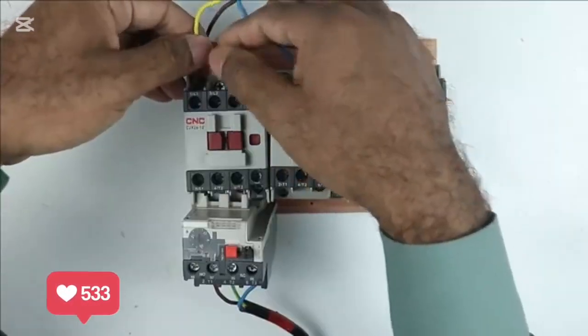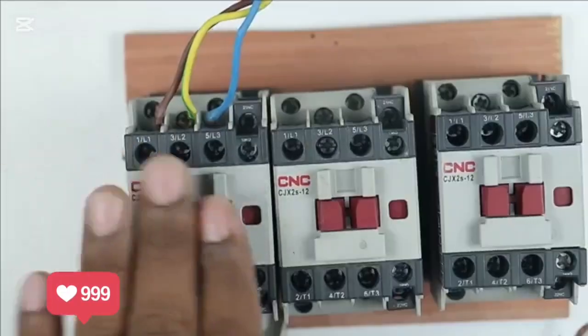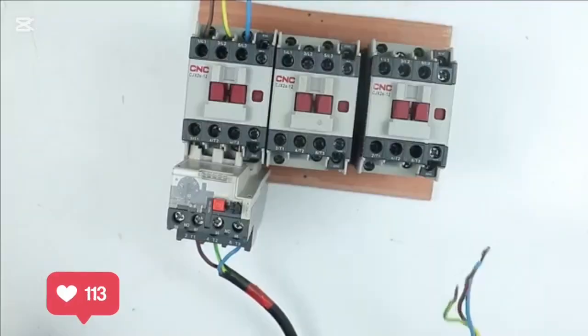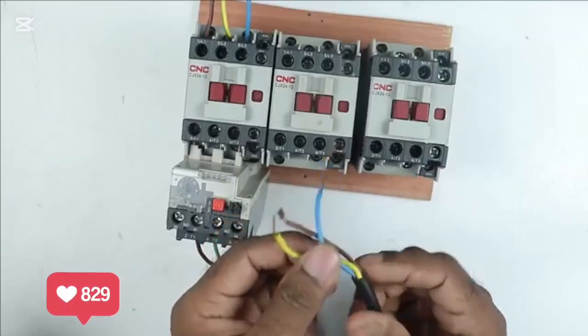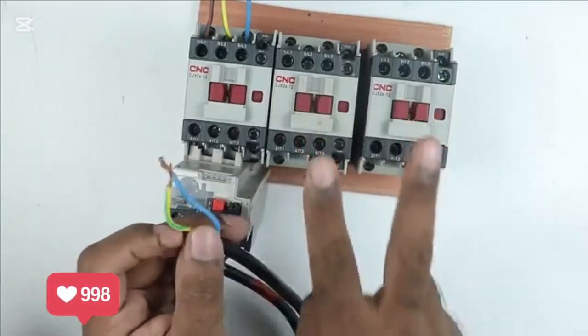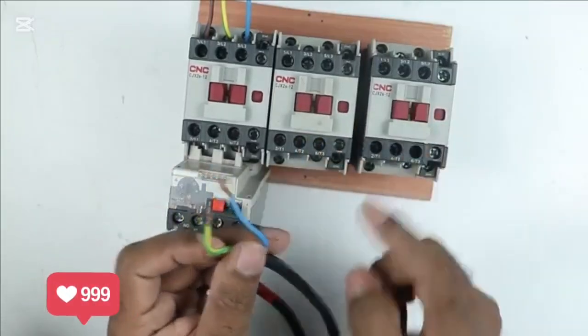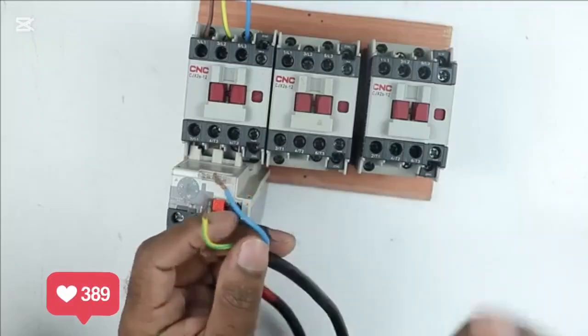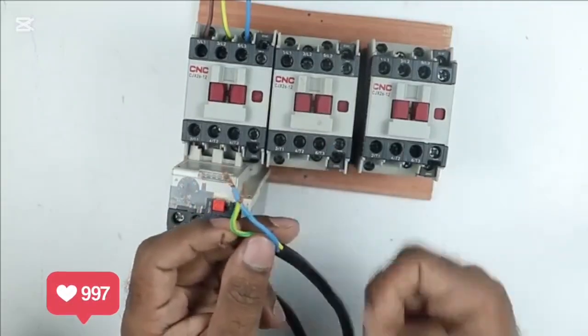At first terminal, I am connecting R phase power supply, at second terminal, I am connecting Y phase power supply, and at third terminal, I am connecting B phase power supply. You have to connect these wires in star connection and delta connection. For this, you need 2 more contactors for connection. One contactor will connect motor winding in star and the second contactor will connect motor winding in delta.